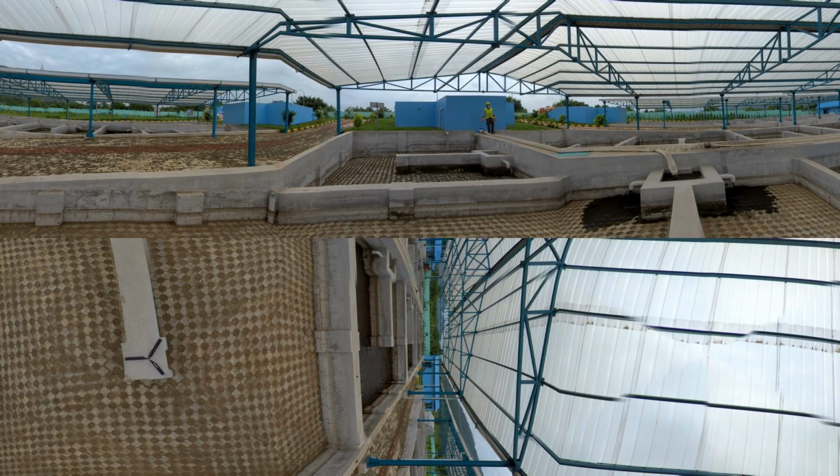Once a year, we have to desludge chambers 1 and 2 completely into an empty sludge drying bed. This helps in maintaining the level of efficiency of the reactor chambers. To desludge, chambers 1 and 2 have to be directly connected using a hose pipe to an empty sludge drying bed and pumped out using a sludge pump. Once the drying bed fills up to 30 cm level, stop the pump. If the pump gets clogged, try restarting it and check for blockage around the valve.